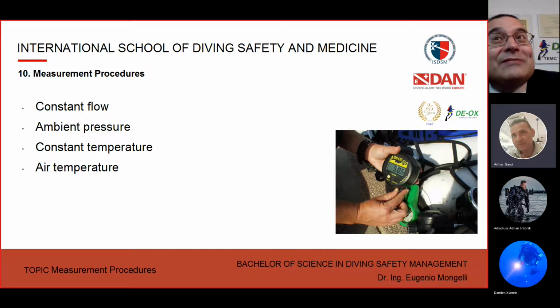Oh, go ahead, Arthur. Sorry. No, when we measure the oxygen concentrators, which produce between 92 and 96% oxygen, we calibrate on air, to tell you the truth. And we do sometimes find problems of accuracy, and we have to adjust for it. But maybe, yes, we overlook the importance of leaving it long enough to adjust. And we're doing it with air. Ideally, we calibrate with oxygen.